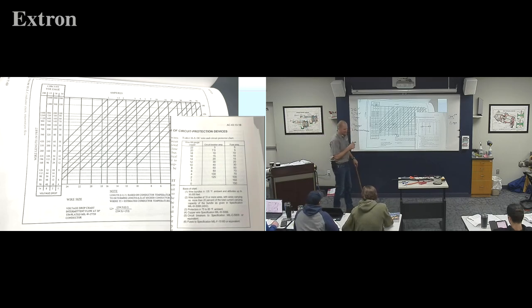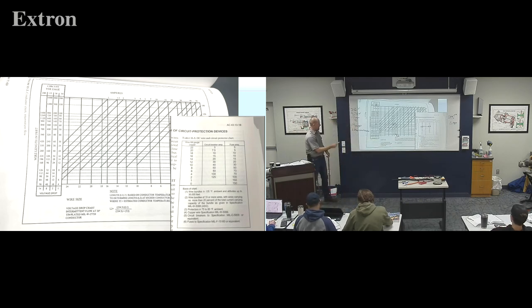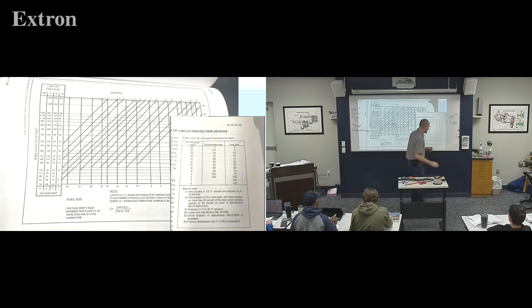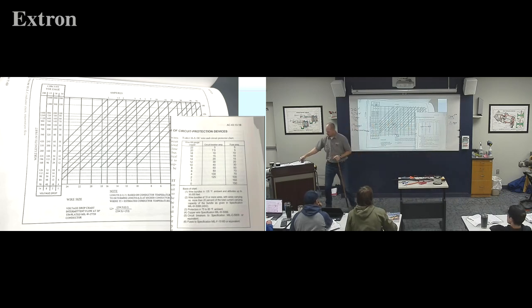Now, there's a slight complication to this, and we're going to show you that here. This worked out great because my circuit breaker is higher capacity than what my component was, right? If I have a 20 amp circuit breaker and I'm only using 13 amps in my component, my breaker's not going to trip. You can end up in a scenario where you get to this chart and you say, okay, I ran a 14 gauge wire, I need a 20 amp breaker, and oh my word, my component draws 30 amps though. So we're going to do one a minute. I'll do it in a different color just to separate the two. We'll make it red for wow, that didn't work. So we'll say 28 volt, 8 foot. Hopefully this doesn't work out.